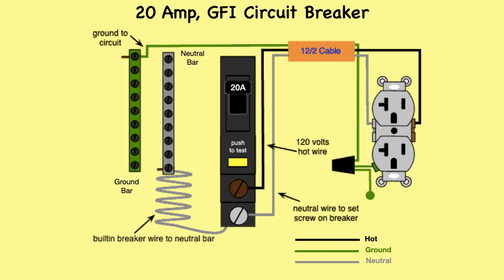This diagram illustrates wiring for a circuit breaker with a built-in ground fault circuit interrupter, or GFI. This 20 amp, 120 volt breaker is a form of GFI that can be installed at the circuit source. This kind of circuit is used for dishwashers, whirlpool spas, and other locations where water contact is likely.